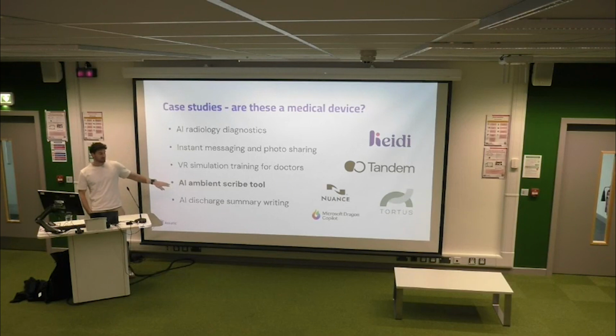If the LLM is being used as a clinical decision support tool, so going a step further when it actually suggests, say, a differential diagnosis or a management plan, it would be expected to be a Class 2A or above. None of those are on the market yet, but people are definitely developing and testing them. And some of them are being used in the US, but there are fewer rules around clinical decision support tools. You can get away with a lot more outside of FDA purview there.